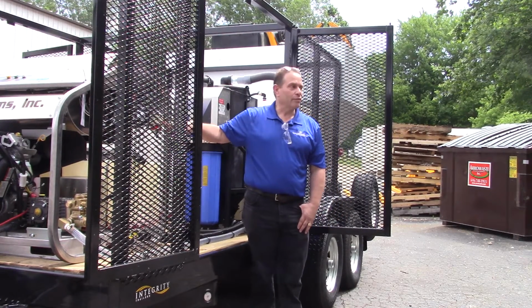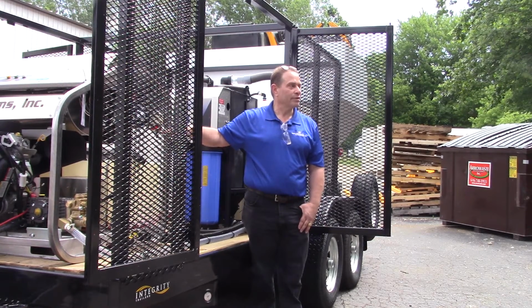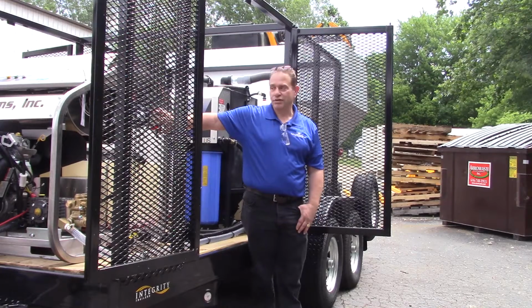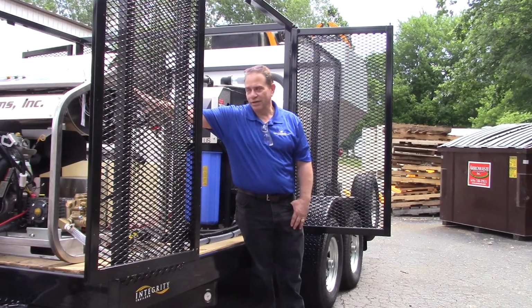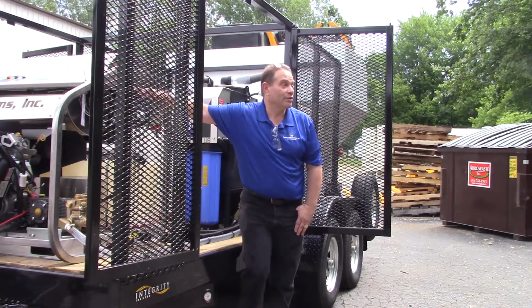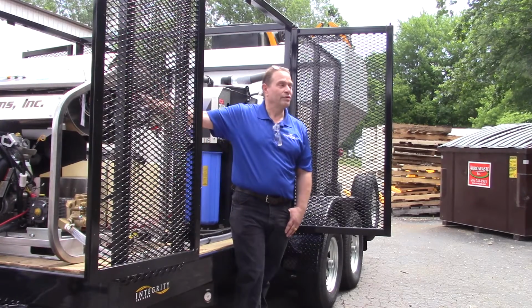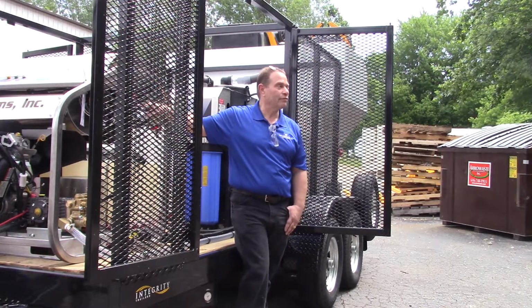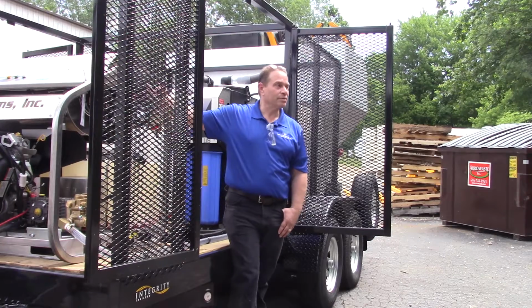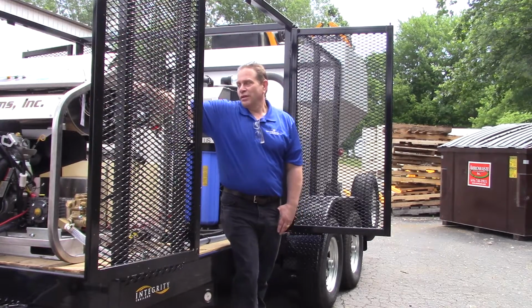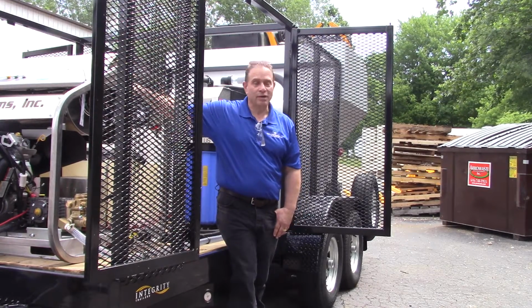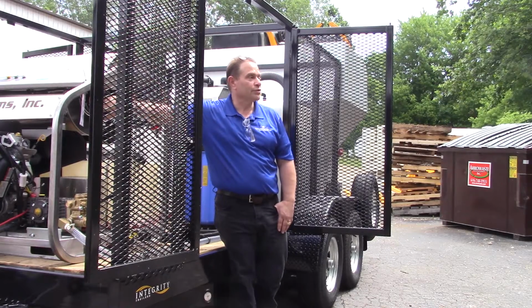The diesel fuel has a Racor fuel filter, which is a fuel filter and oil water separator. So that's also a deluxe version. The Beckett burner, basically you need spark, fuel and air to get fire, and that's what this is doing for you. You've got a blower fan that actually produces the airflow, with air band adjustments to control that. The igniter creates your spark, and then your fuel pump here is your fuel source.